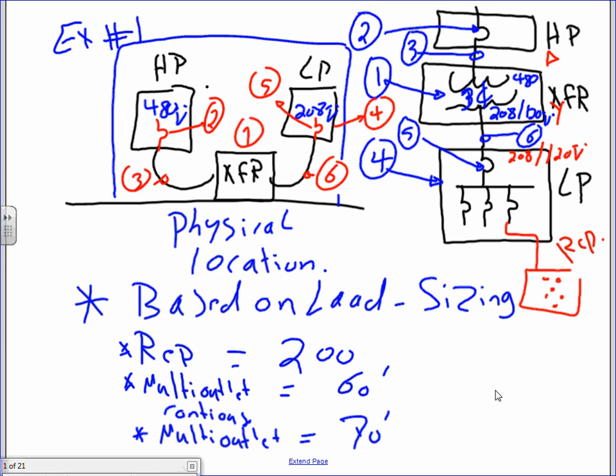Everybody understand the combo that we have here? And then, what's your job, Karen? Your job number one is to size the transformer for this receptacle panel. We need a transformer. And after we come up with the size of the transformer, we need to size the overcurrent protection device for the transformer on the primary side. Then we need to size the feeder on the primary side of this transformer. Then we're going to go to the secondary side, guys, and we need to size the panel itself.